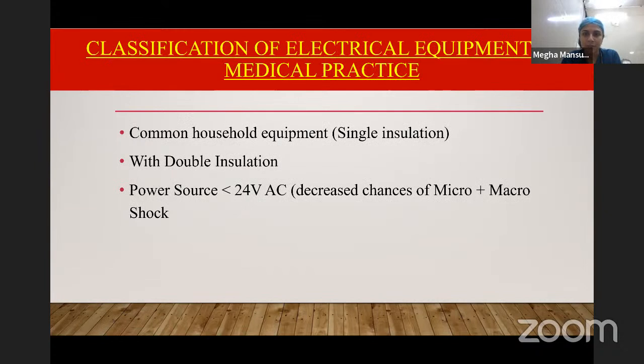Classification of electrical equipment in medical practice. It can be class 1, 2, or 3. Class 1 involves common household equipment, which has only single insulation. Class 2 equipment has double insulation. And class 3 equipments are those which use a power source of lower than 24 volt AC current.